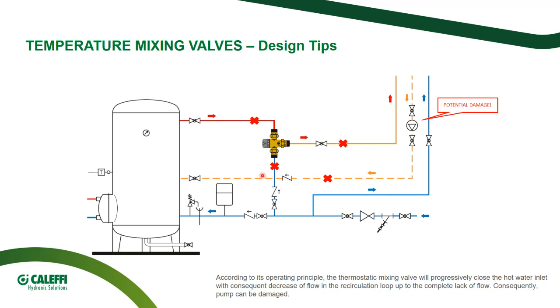If the cold water inlet is closed and the hot water inlet is closed, the mixed outlet will also be closed. So I will have a complete lack of water circulation. So my users will not have hot water, so poor comfort, and furthermore, my recirculation pump will push towards a closed system, so it might get damaged. So these were just some design tips for mixing valve installation and design.